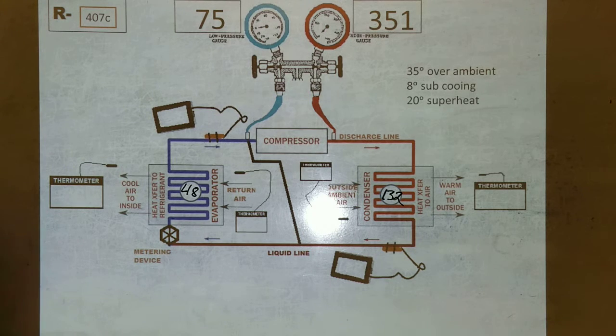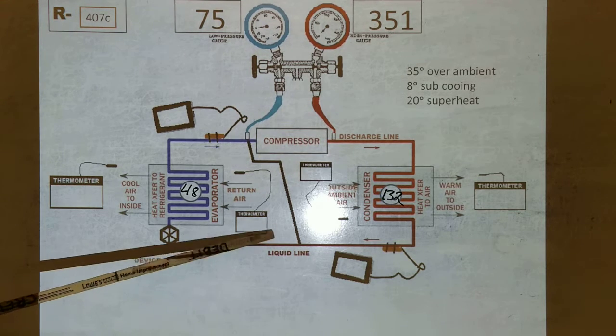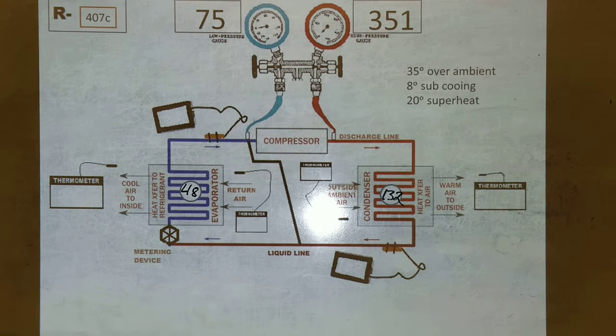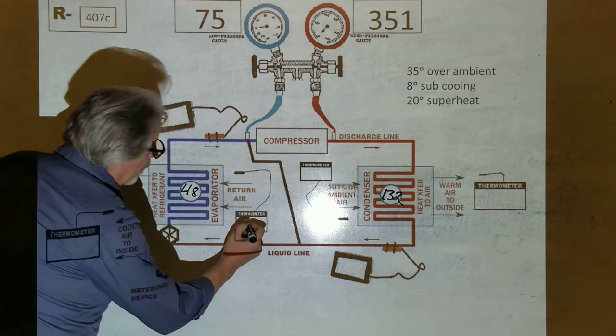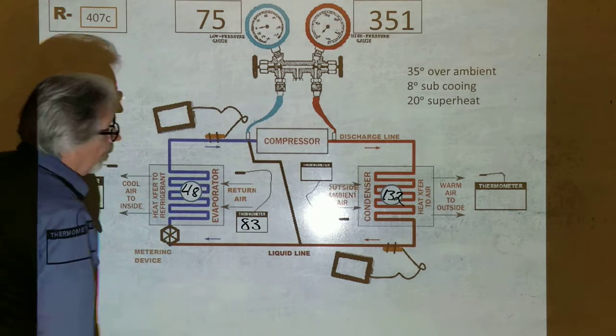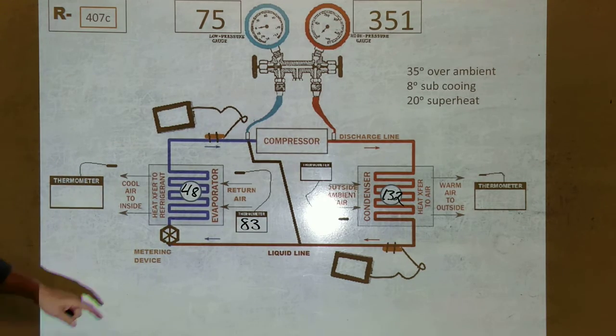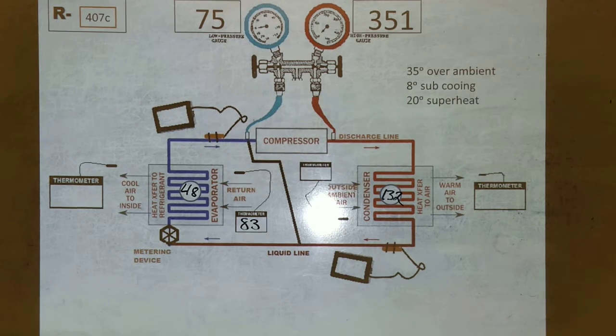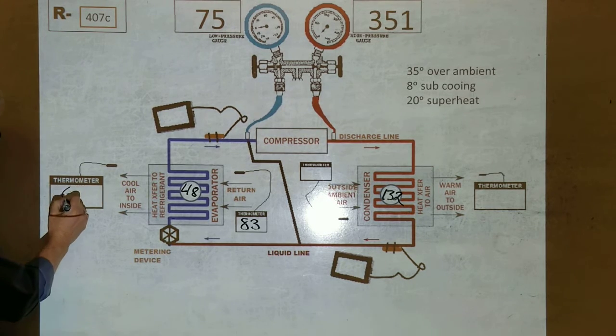So from that point, we can go 35 degrees. Do we know what our return air temperature is? 83, or should be. So we're gonna check it right at the unit, but we know we should have 83 degrees. If we don't have 83, then we got a problem, something going on, right? And the supply air is what? 63.